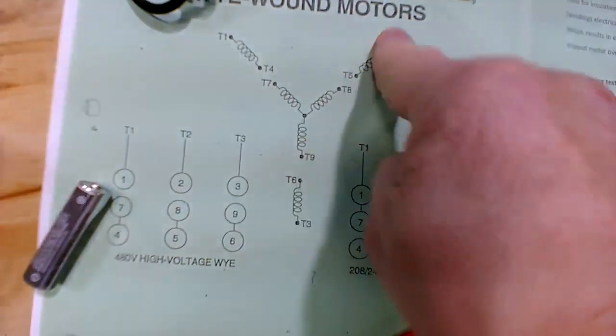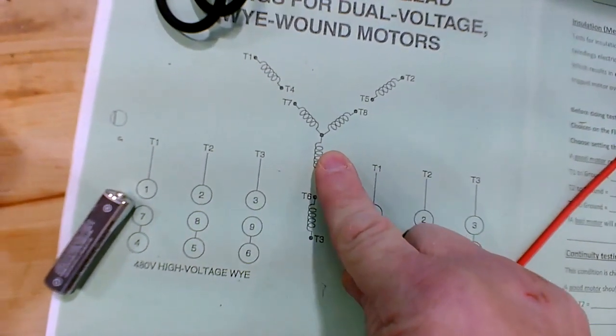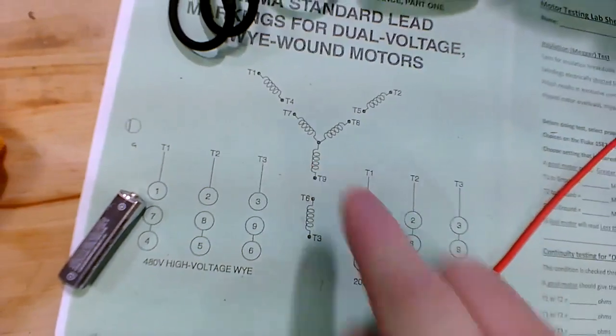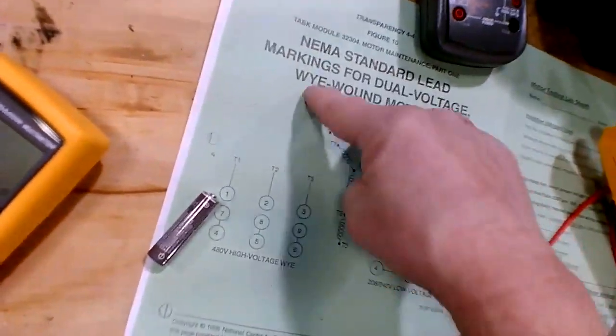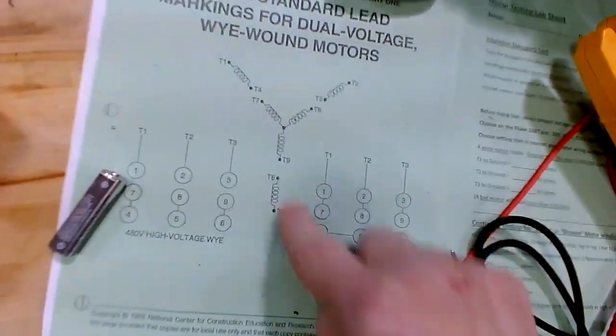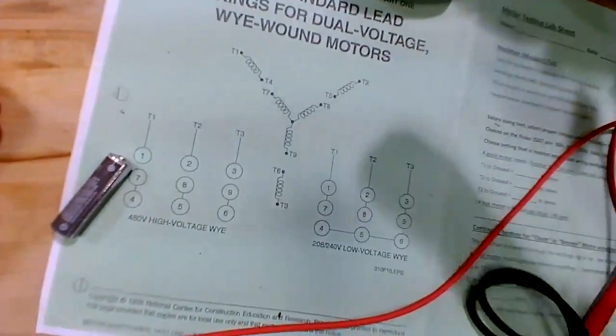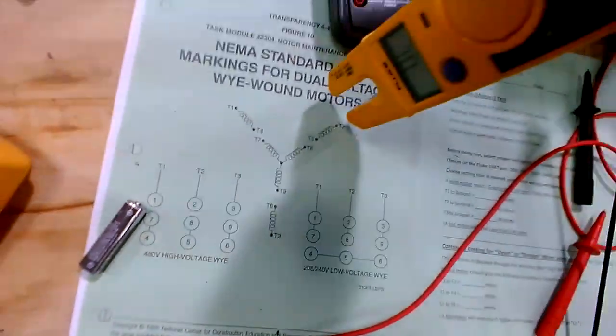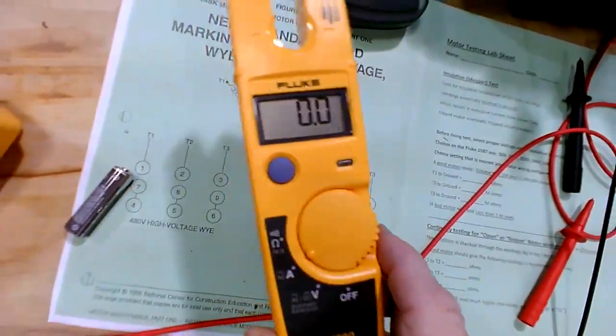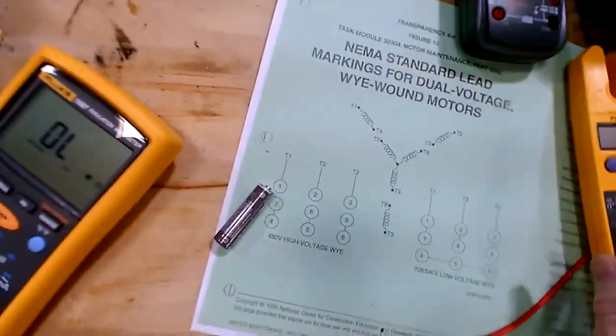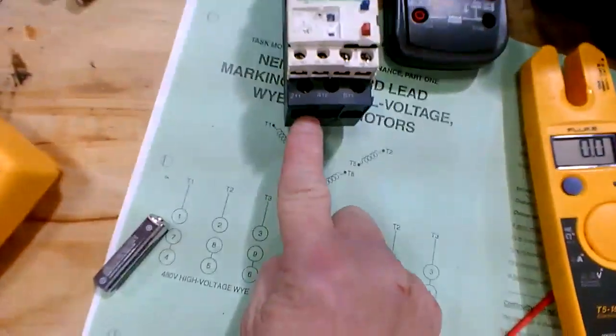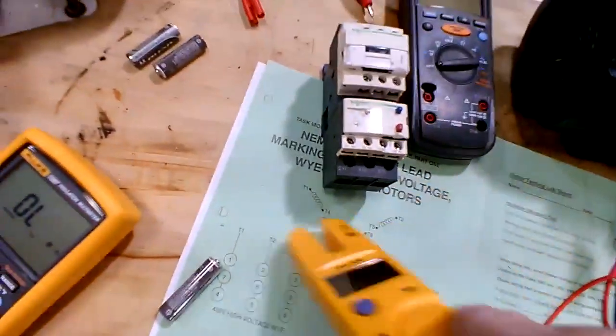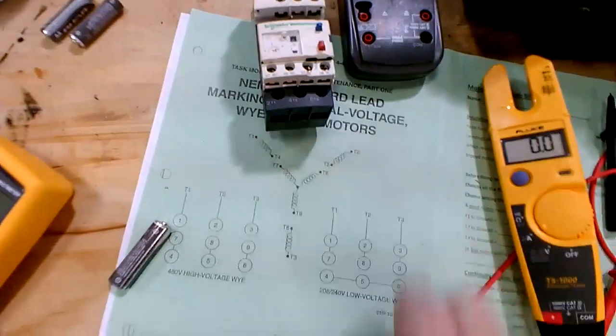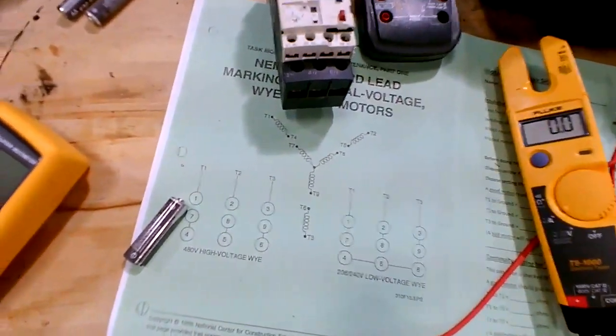So if you have an imbalance in resistance here, here's what can happen. Here's the symptom when the thing runs. It's when you go check the amps, when you go out here and check the amps, and watch this. If you got, say, 20 ohms and you got 100 ohms and 100 ohms, you cut that thing on and you run power and you check the amp draw, the amps is going to be very much unbalanced. So your amp draw coming from that starter, when you check the amps leaving that starter per leg, them amps, they're not going to be balanced, they're going to be unbalanced.